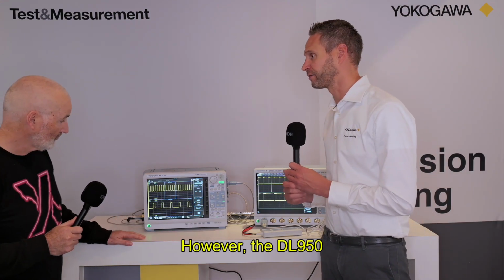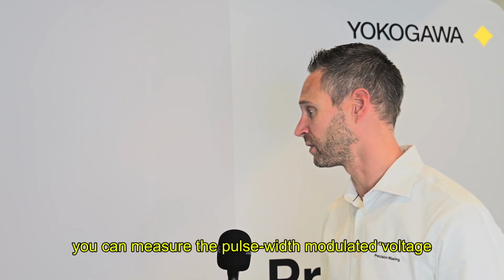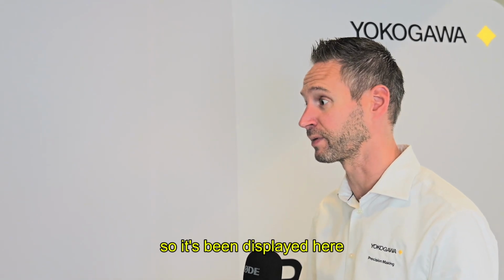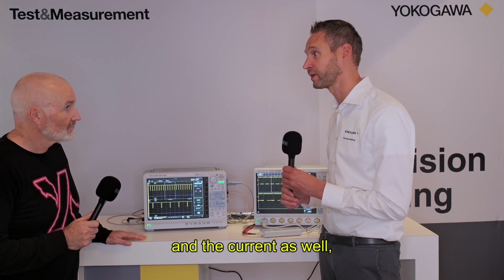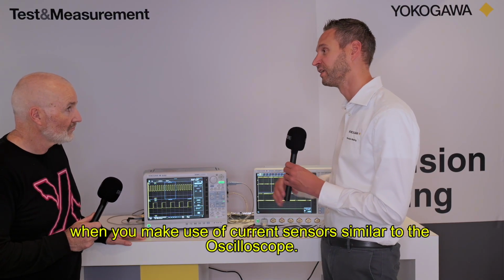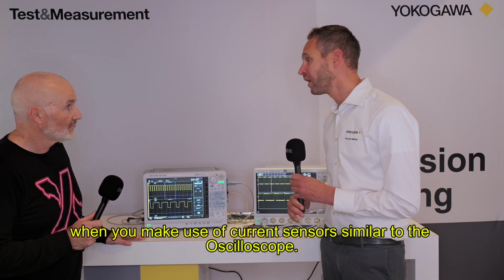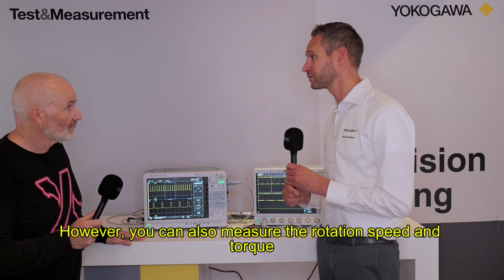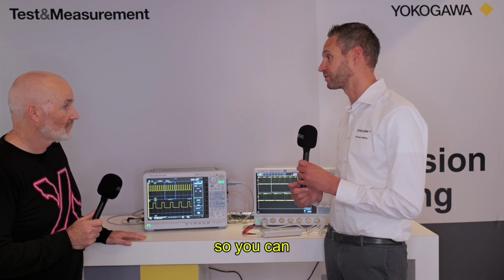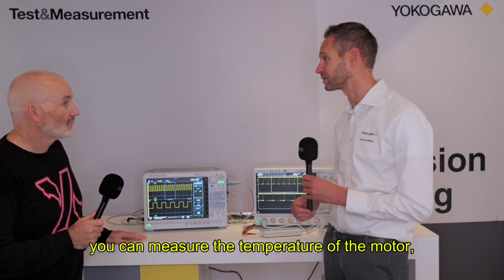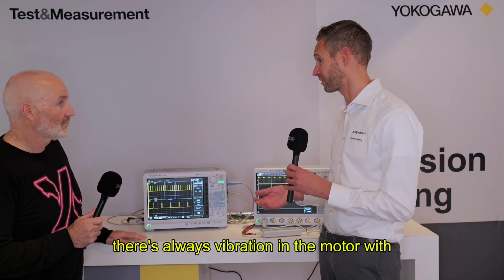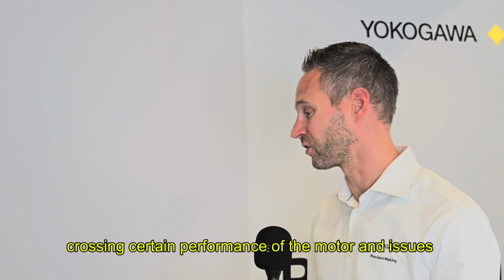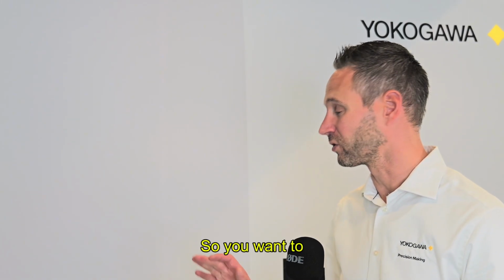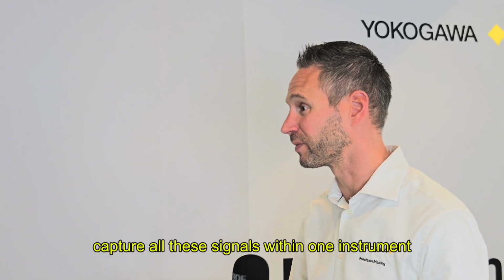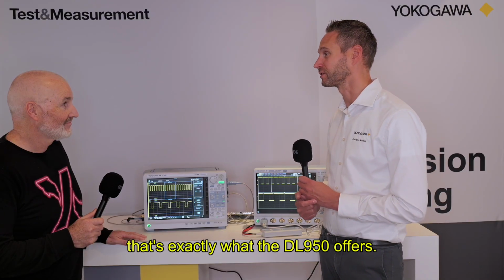With the DL950 you can measure the pulse width modulated voltage, which is being displayed here, and the current as well when you make use of current sensors, similar to the oscilloscope. However, you can also measure the rotation speed and torque, so you can measure mechanical power of the electrical motor. You can measure the temperature of the motor, and there's always vibration in the motor, which causes certain performance issues with electric motors. So you want to capture all these signals within one instrument, and that's exactly what the DL950 offers.